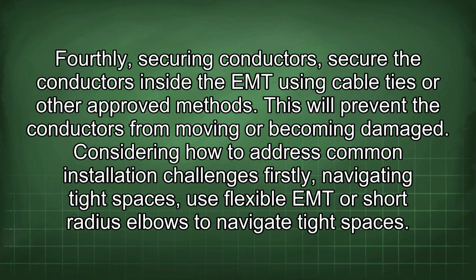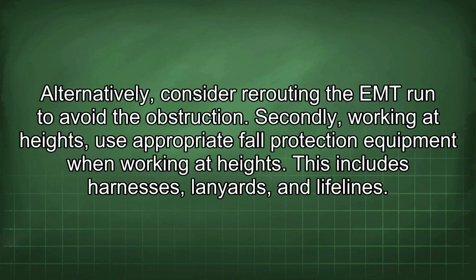Considering how to address common installation challenges. Firstly, navigating tight spaces. Use flexible EMT or short radius elbows to navigate tight spaces. Alternatively, consider rerouting the EMT run to avoid the obstruction. Secondly, working at heights. Use appropriate fall protection equipment when working at heights. This includes harnesses, lanyards, and lifelines.